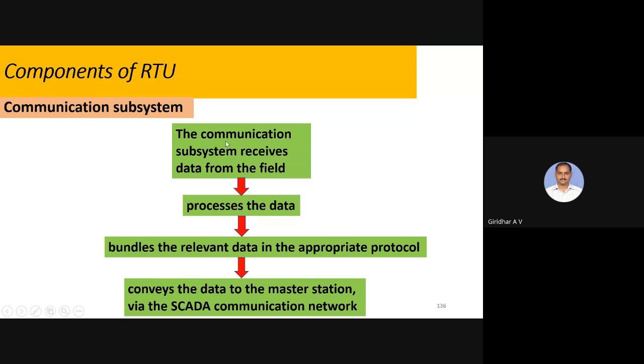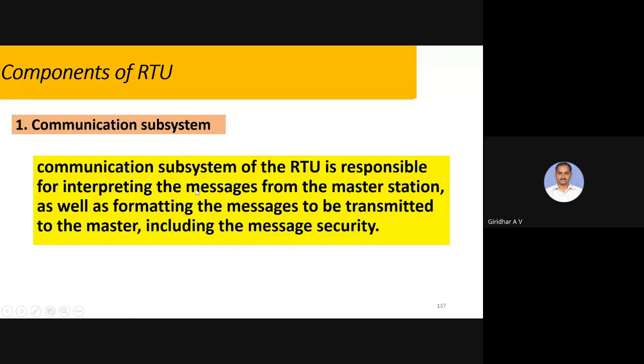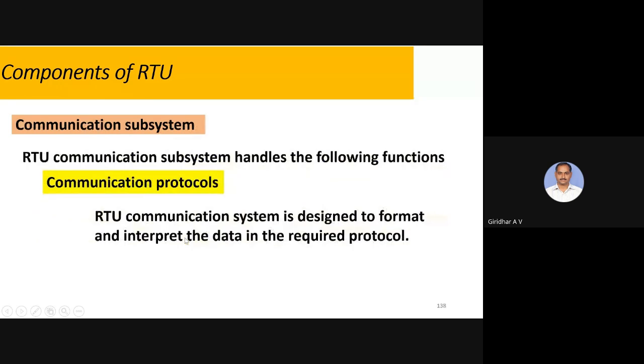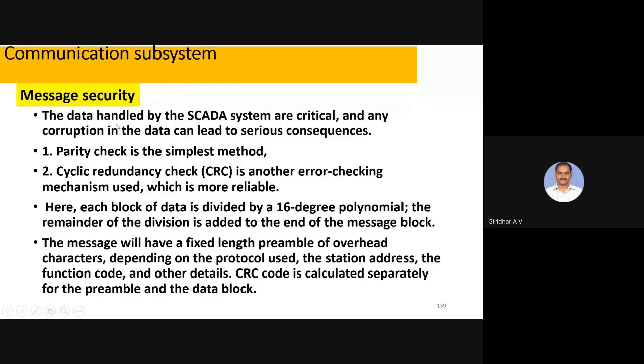So the communication subsystem receives the data from the field, processes the data, bundles the relevant data in appropriate protocols, and conveys it to the master station. So there we will see the communication protocols, how we are using them, and in that way, the particular data, whichever is important, will be transferred. All the message security will be done in the RTUs itself. Parity checking and cyclic redundancy checking will be done in the SCADA communications also.